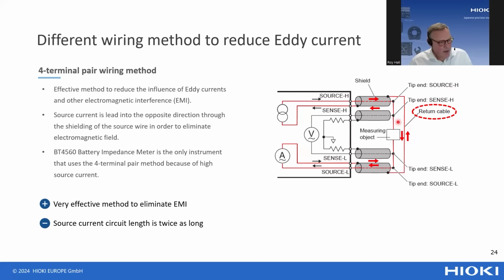Also, nearby the battery, you have to have a return cable to connect the current signal from this coaxial cable to the shielding of this coaxial cable. Then the current flows back into the battery tester, also for this cable having an opposite current, which cancels out the electromagnetic field.